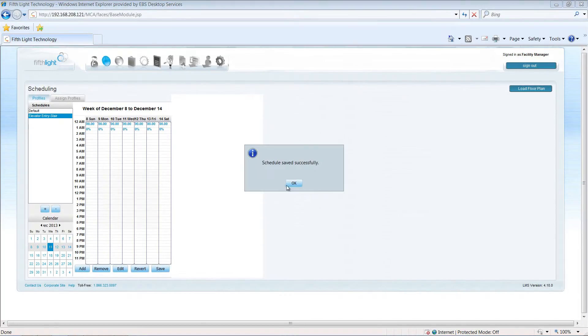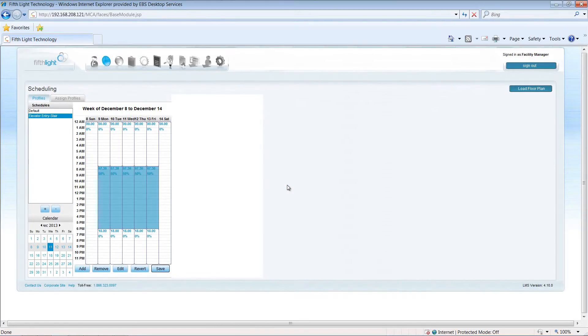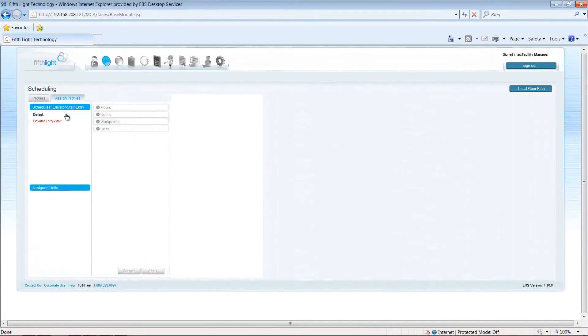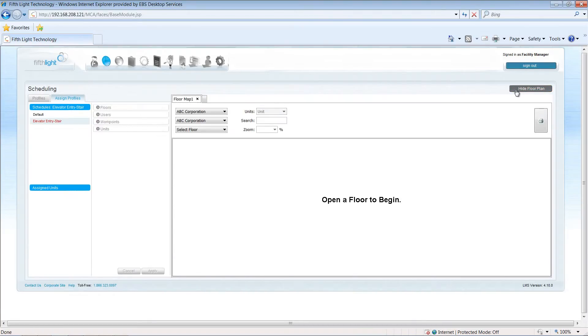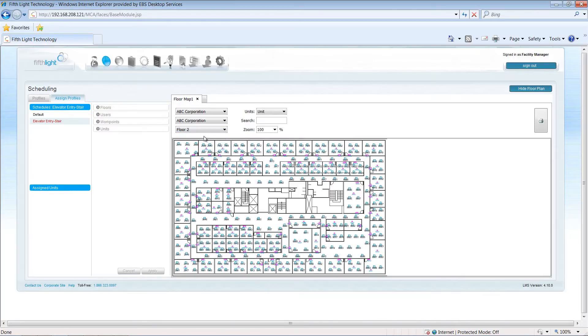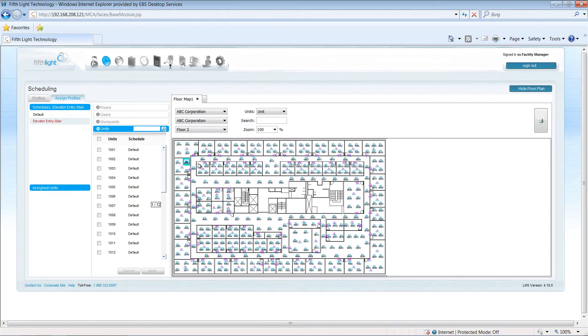Once I've saved the profile, within the Assign Profiles tab, I'll select it and load the floor plan for my area. Using the mouse, I'll click and drag to select the lighting I want to control with this profile, holding down the Shift key on my keyboard to select additional areas. Then I'll apply these changes.